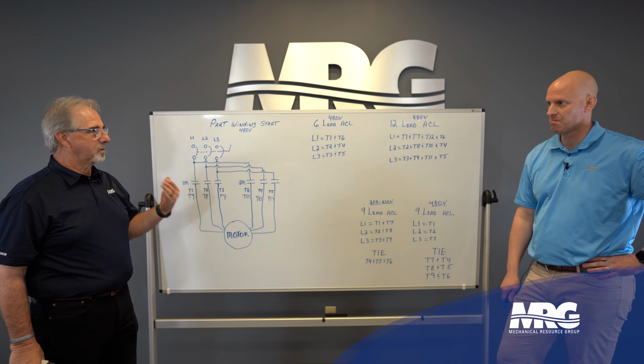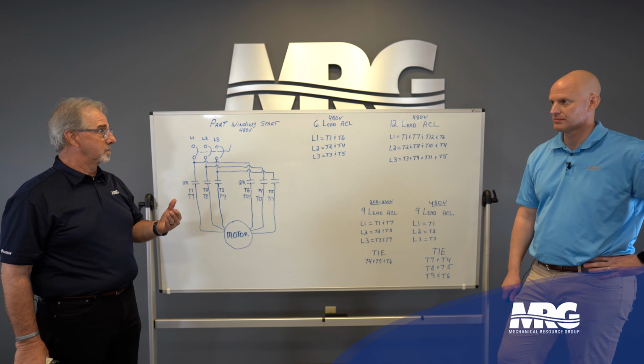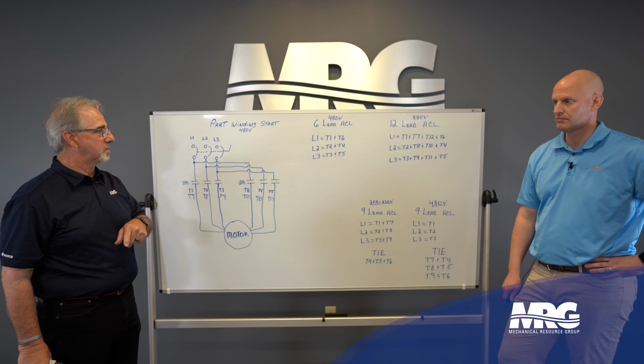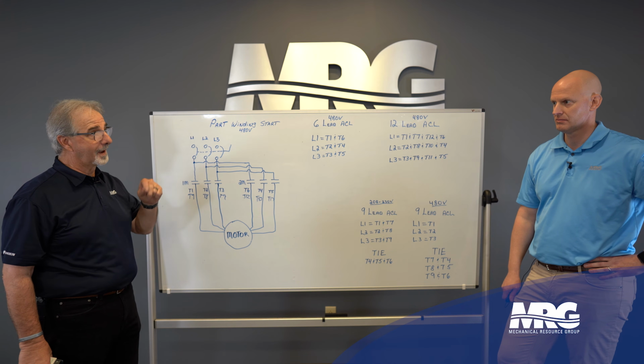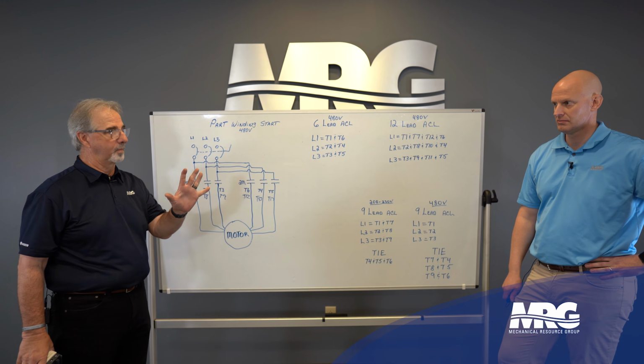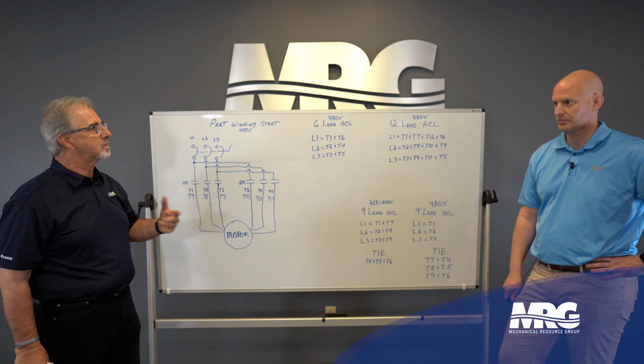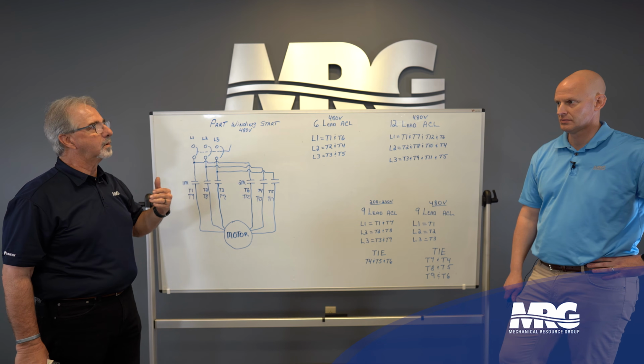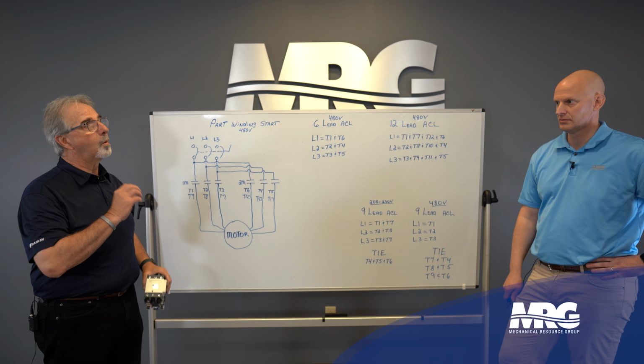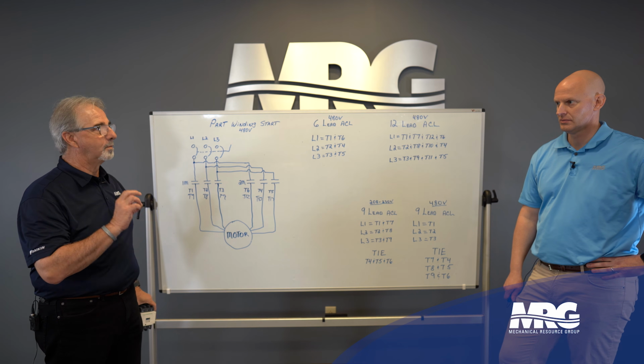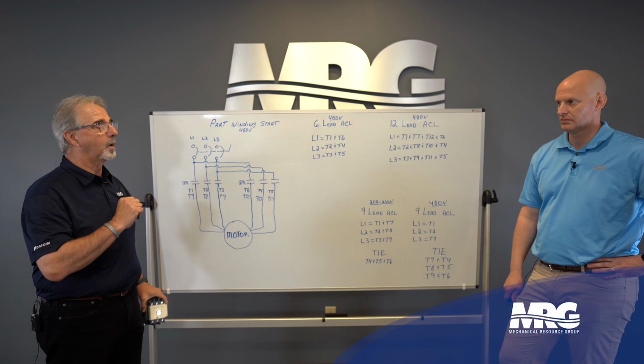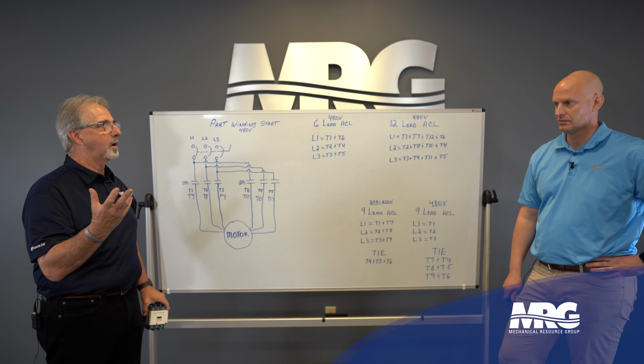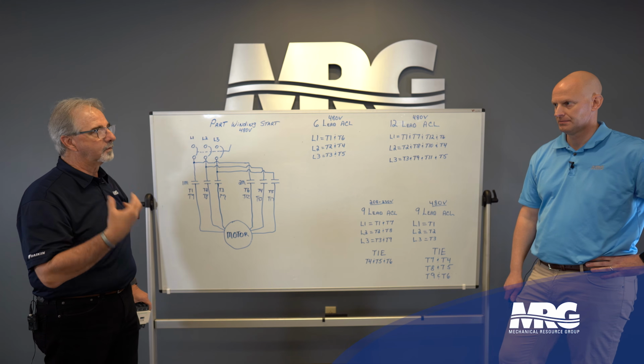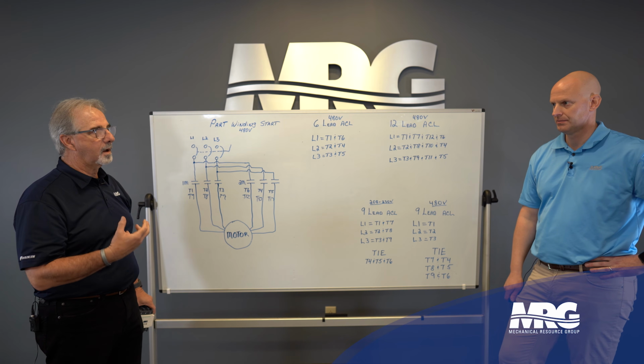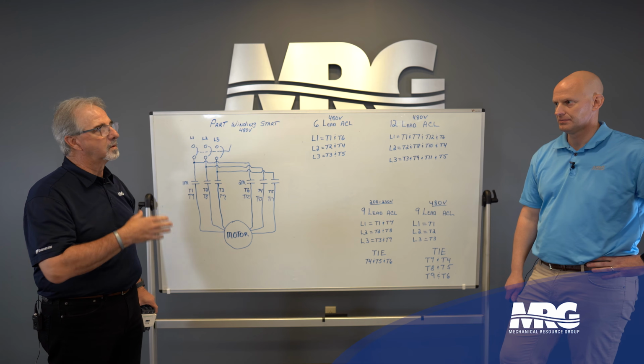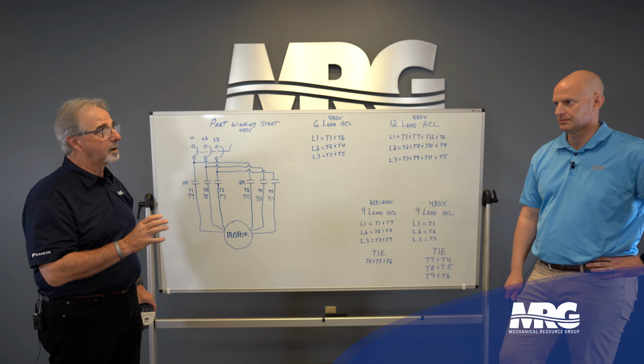Now, motor connections, NFPA 79 addresses this. It's NFPA 79 2007, and it's clause 13.9.5.2, if you ever want to look it up, okay? And what that tells us is it says it must be an identifiable connection method. Twist-on wire nuts are not an acceptable method. This is what we refer to for motor leads. Wire nuts are great in control circuits and house wiring and that type of stuff. Motor leads are a varying current of which they can get hot. There's a lot of things. So even NFPA they've recognized, hey, don't use wire nuts on motor connections.